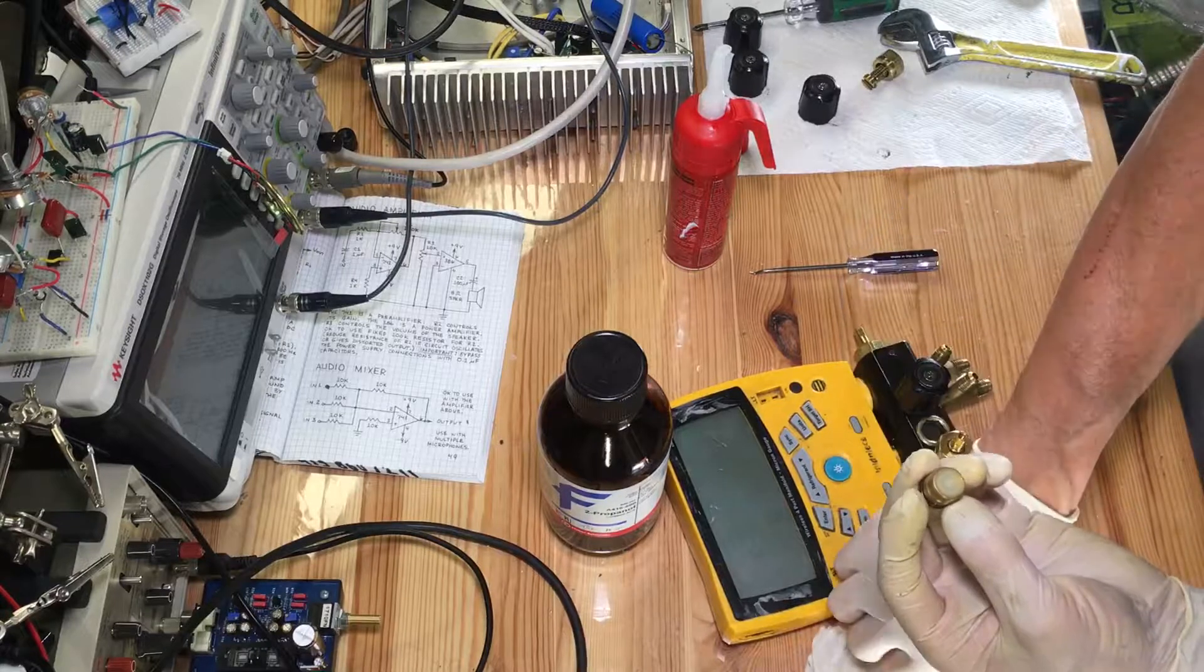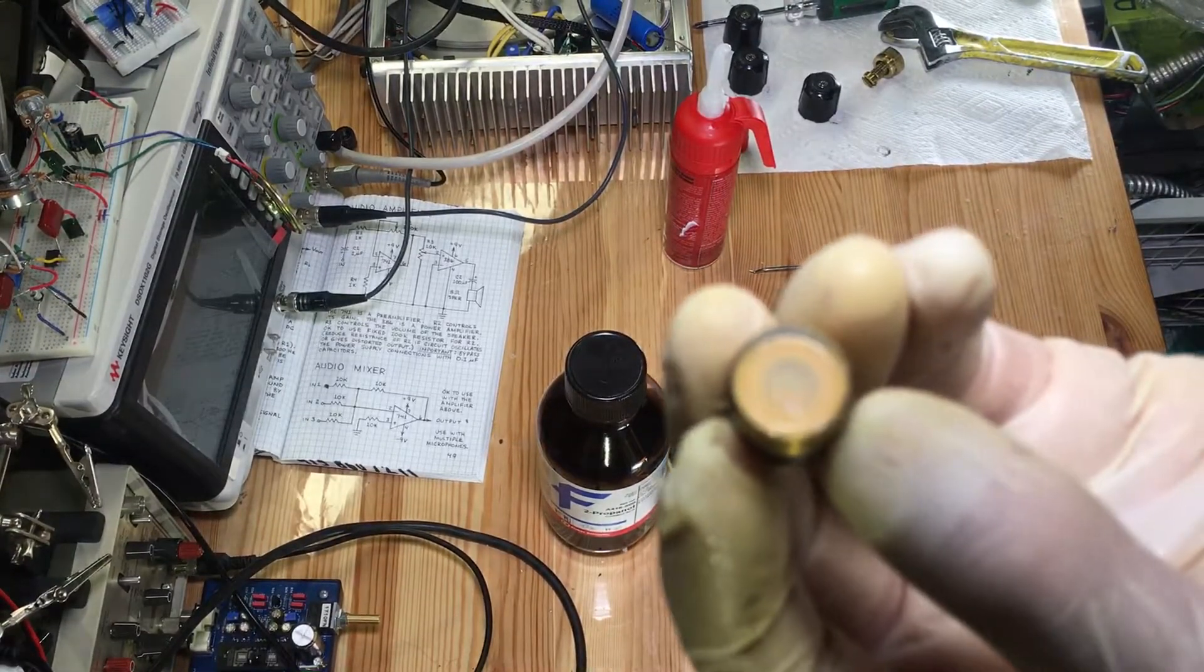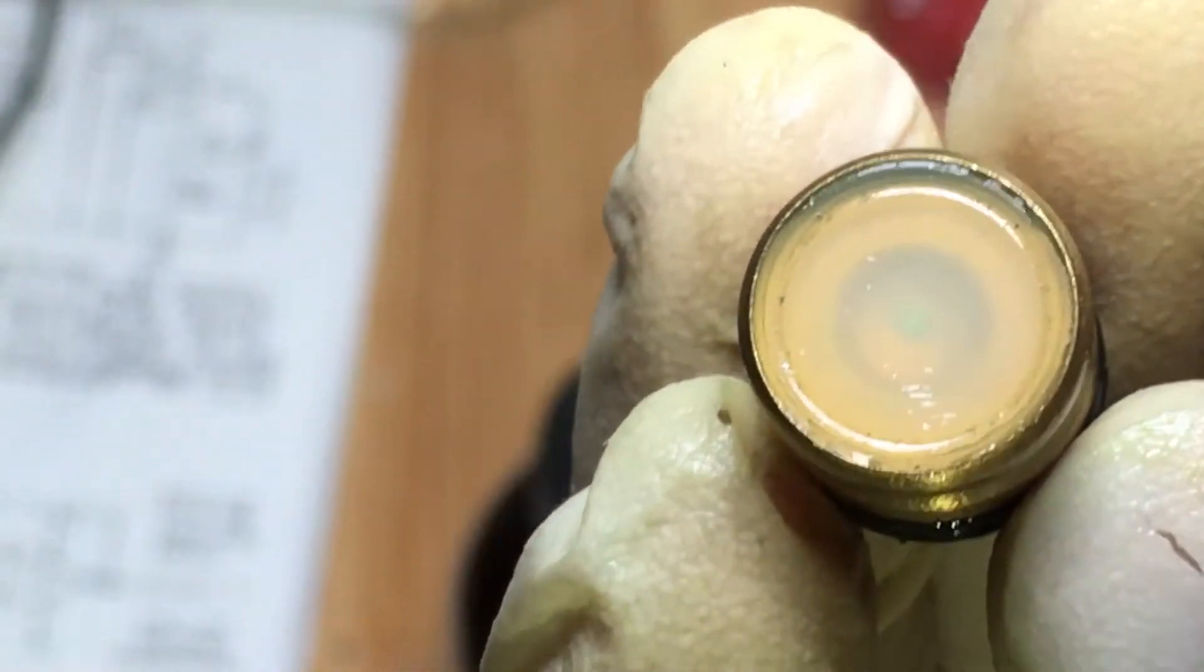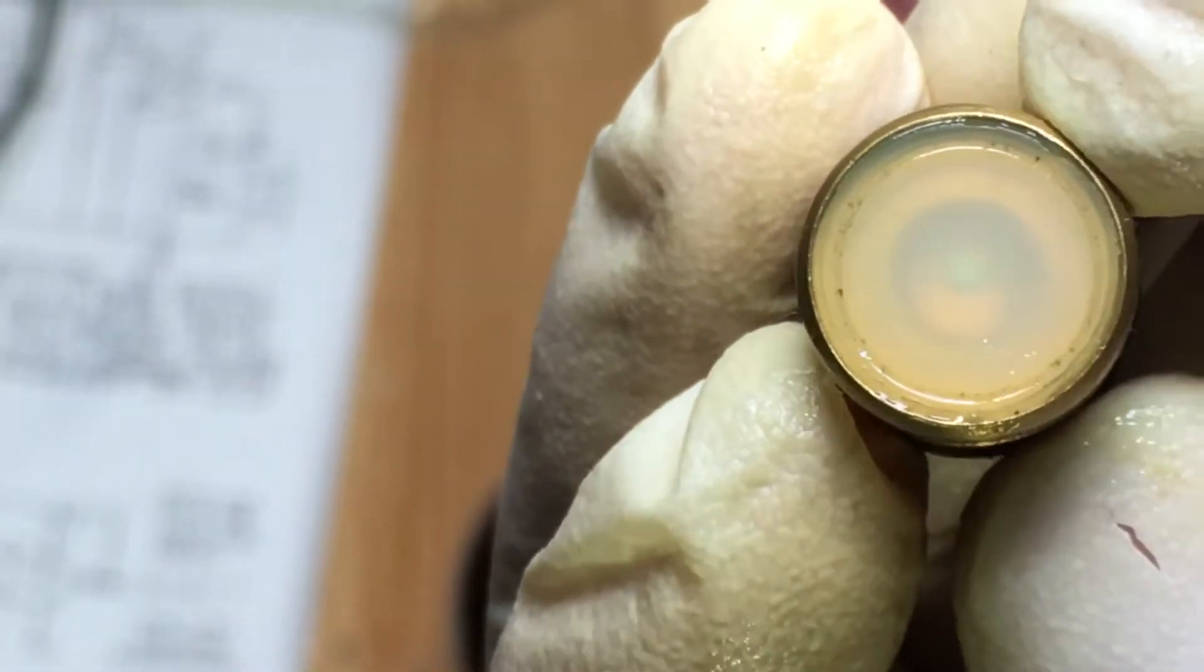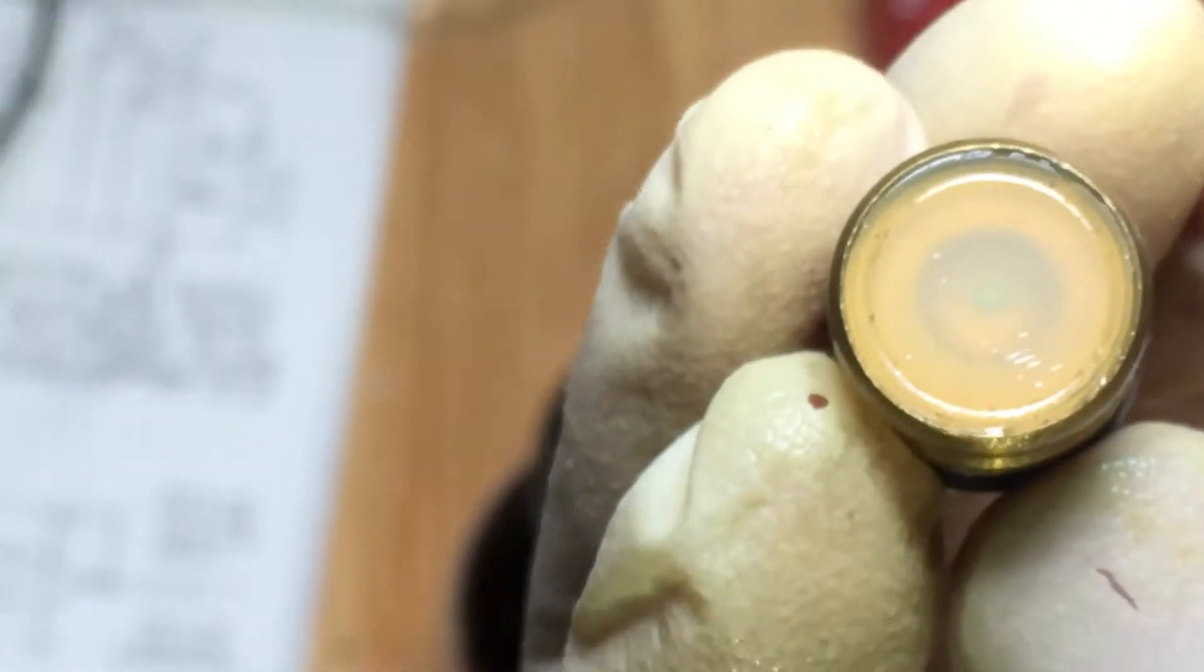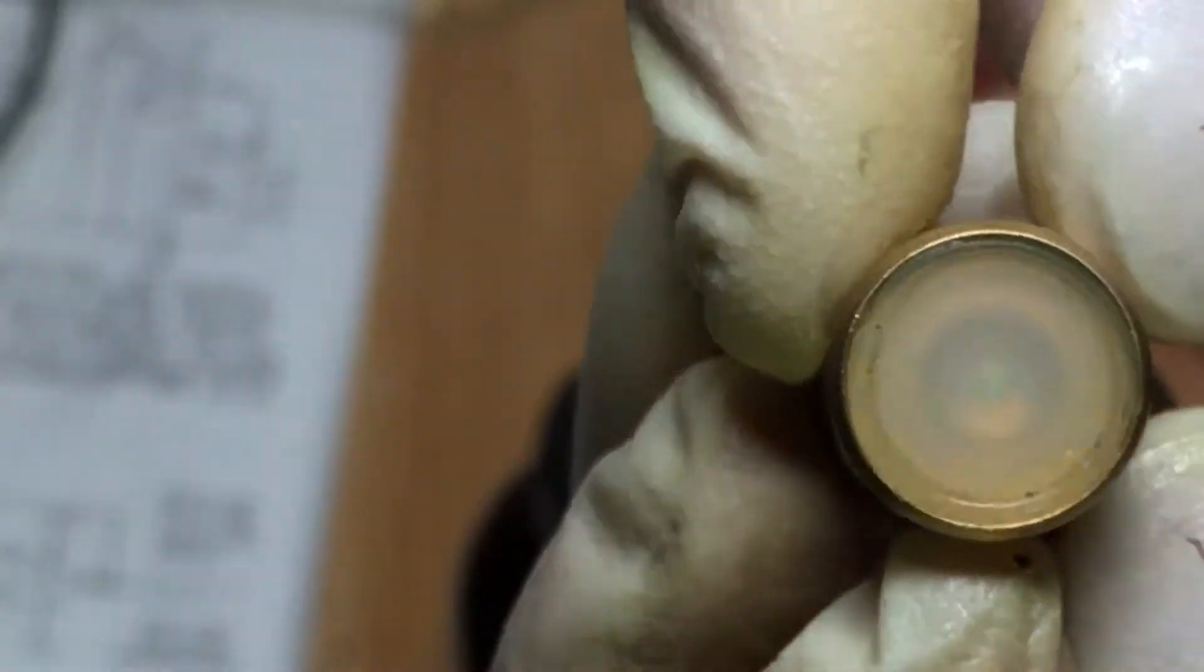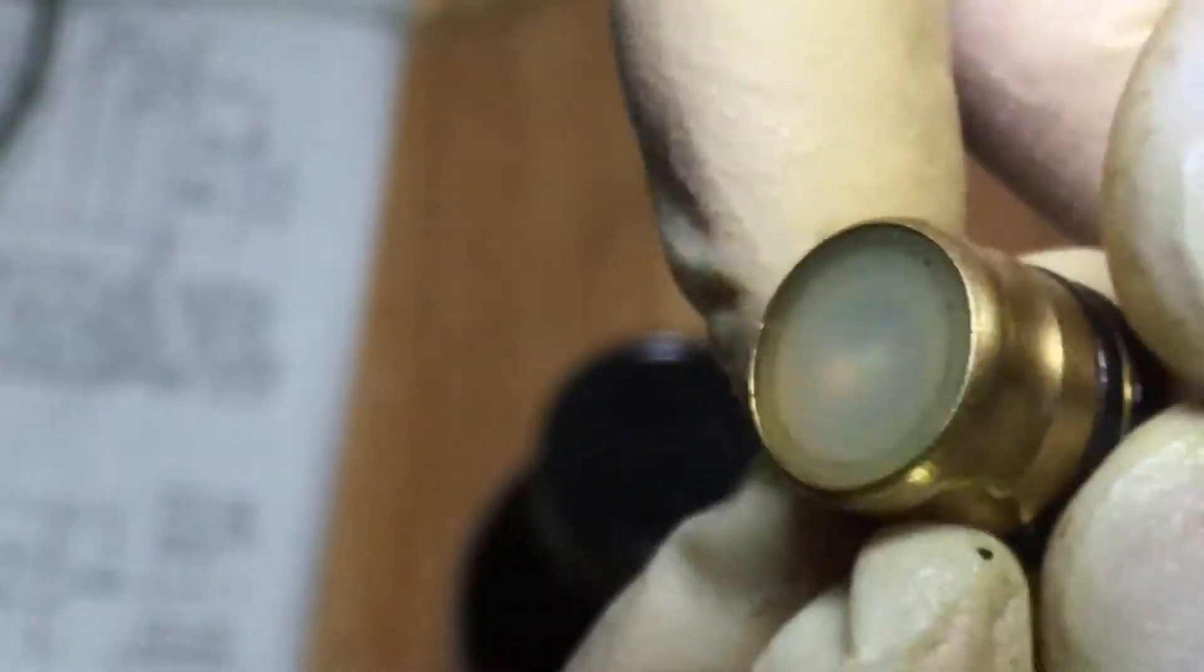Now one other thing you'll notice. Get this to focus. Now if you look really careful, you'll see a little groove. And you'll see metal particles, little black particles in that groove that is formed. That is, the whole flat surface is not the sealing surface. It's that round ring that you see going around. And you'll see little black debris. That's usually from your dirty systems, and that's where you'll lose. You'll either bypass refrigerant, or you won't be able to hold a vacuum seal, and it'll bypass. Time for a new piston.